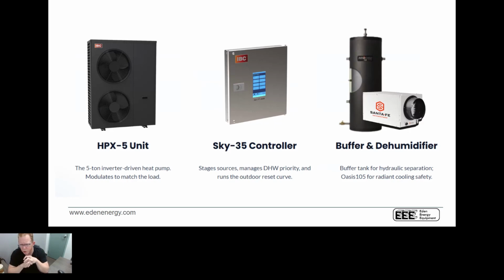So in my house, I have what's called an HPX5. It's a 5-ton air-to-water heat pump, controlled by a Sky 35 controller. The Sky 35 controller controls heating, cooling, domestic hot water, basically everything I need, including the buffer tank. The other really important thing beyond the buffer tank is sensible and latent cooling. How are we going to control sensible and latent cooling? That's where a centralized dehumidifier, for example a Santa Fe product or an Aprilaire product, would be a really good application to make sure you have a successful installation.